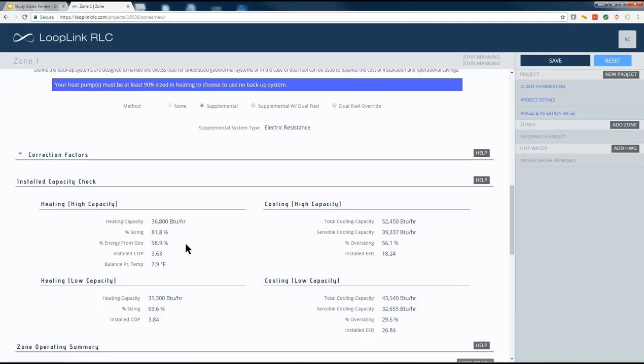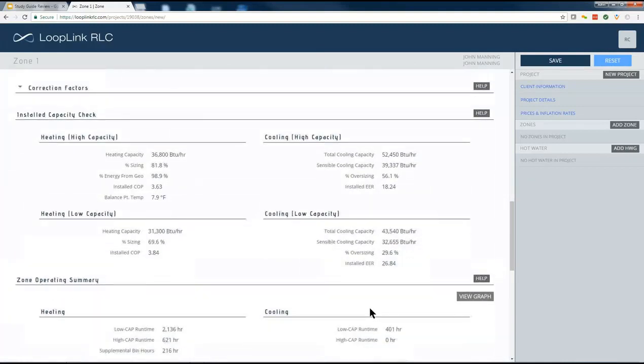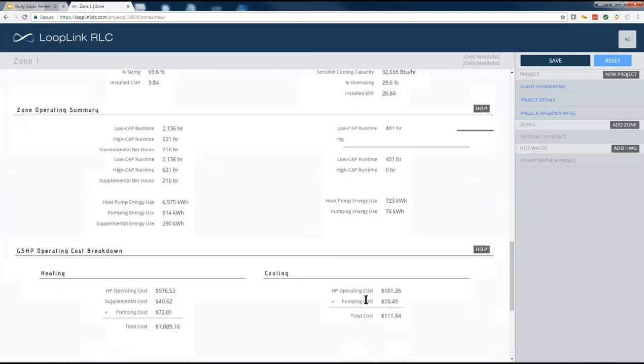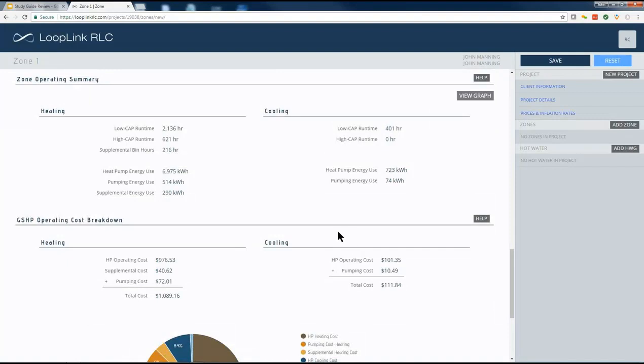Still covering most of the energy requirements in heating and much closer to that 25% guideline that we try to shoot for in cooling side. So for the sake of this example, I'm probably going to stick with a 4-ton unit for this space. And you can see, obviously, the heat pump runs a few more hours in high speed. We get a few more supplemental bin hours, but look what happened to the operating cost. It wasn't drastically affected at all. Supplemental costs went up a little bit, but we're still at about $1,200 total operating costs in heating and cooling combined.